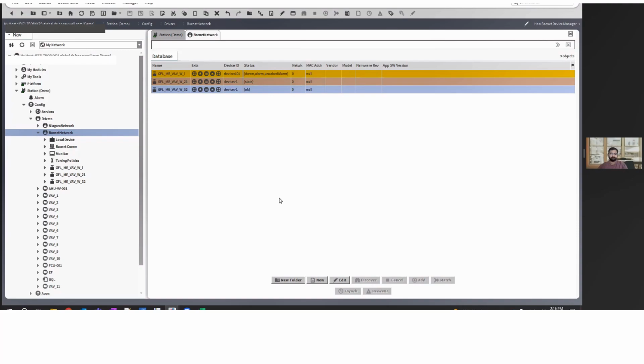They don't even have to do a manual duplication of the controllers; everything would still be in the report of all the 1,000 controllers. All they do is import that CSV file, and it should bring up each and everything in that spreadsheet. So you need to put in an immaculate amount of time into the spreadsheet to make sure everything's right, so you don't have to fiddle around in the Niagara software during the crunch time of commissioning to see which points are coming in and which don't have the state text or something like that. That's really helpful for building a database.